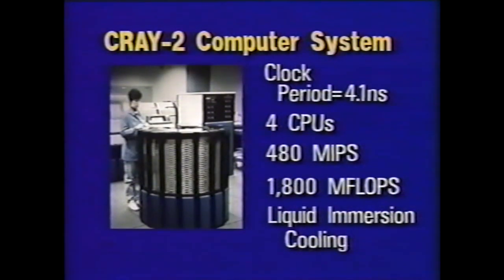And today, I believe that Cray-2 reliability is as good or better than most anything else you can find. A lot of the reason for that is the liquid immersion cooling. There's very little temperature difference between the parts during warm-up and during normal operation, so we have good temperature stability, and that's a real key to reliability in the long run.